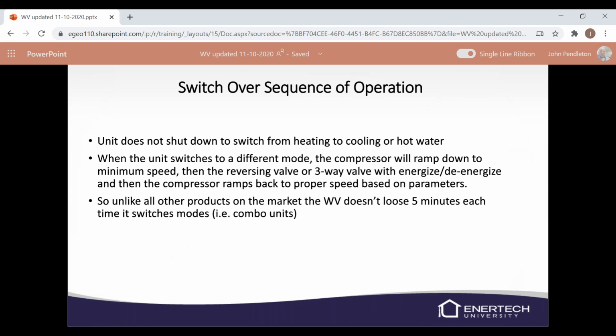Switch over. If you're switching from heating, cooling, or hot water, the unit does not shut down. The compressor will ramp down to minimum speed, so that's 1650 RPM. Then the reversing valve, if you're switching to cooling, or the 3-way valve, if you're switching to domestic hot water heating, will either energize or de-energize, and then the compressor will ramp back up. So we don't lose that 5-minute anti-short cycle between modes like we do in some of our other units, you know, a WT unit or a packaged unit or something like that. So we don't really have any real downtime. That's real nice, especially when you're switching from your load water heating to your domestic hot water function. You'd hate to have that 5 minutes waiting on it to heat up your hot water for your shower.